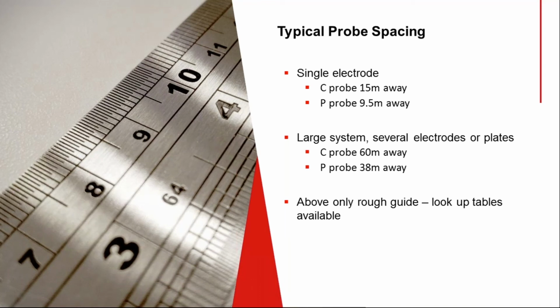The best thing to remember about those tables is that they are suggestions. They're there to give you a pretty good chance of not having to repeat the test. They're not ironclad scientific. So if the table tells you to go out 500 feet and you don't have 500 feet, go out 300 feet. And if you get a good fall of potential graph, you're good, don't worry about it. We'll show you, I think, the next slide.